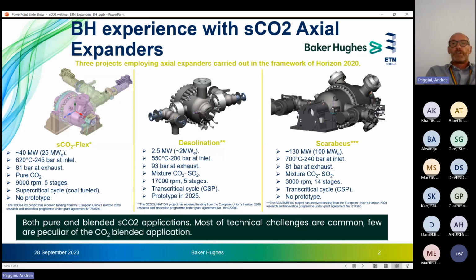So inlet condition above 200 bar up to 250 bar, and inlet temperature from more than 500 degrees to even 700 degrees C. So these conditions are not far away by the normal values encountered in ultra supercritical steam technology. Nevertheless, sCO2 expanders have some peculiarities requiring special care in the design, and I will try to summarize something.